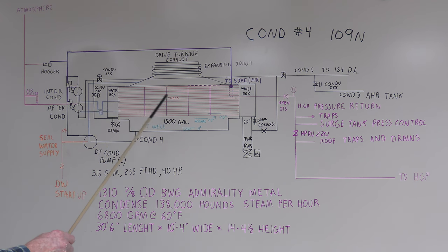The tubes - there's 1,310, 7/8 inch OD BWG, they're Admiralty metal. It required 6,800 gallons a minute of 60 degree water for condensing the steam. Your raw water service came in, went down the bottom to the other water box, then it reversed and came back to the top of the tubes and then to the raw water return.